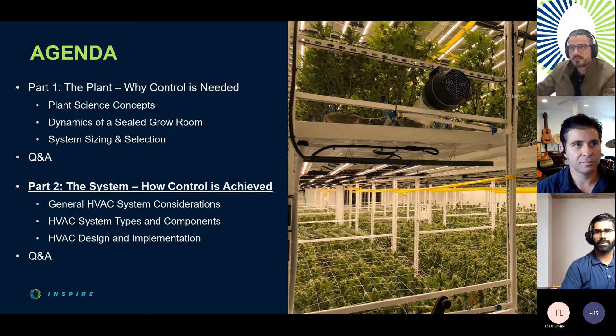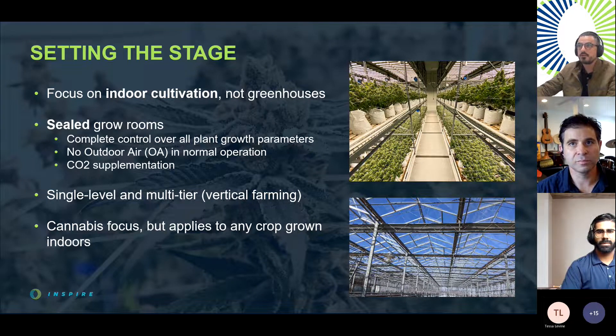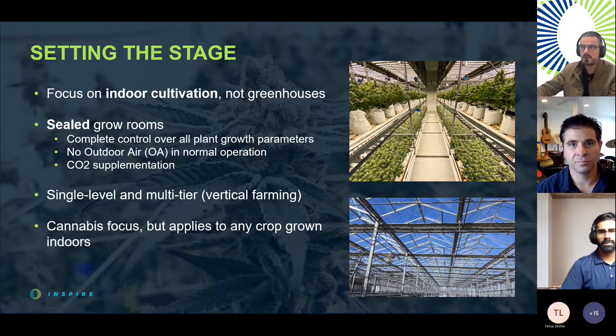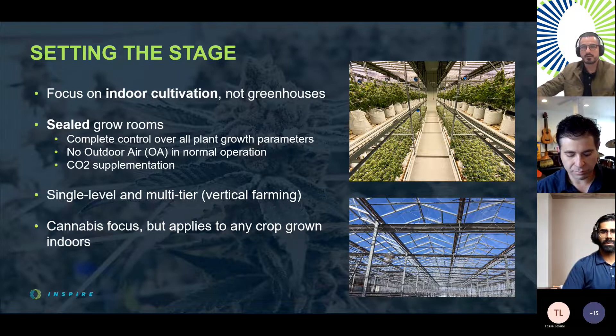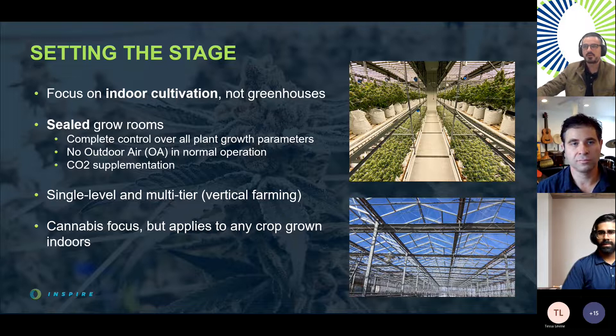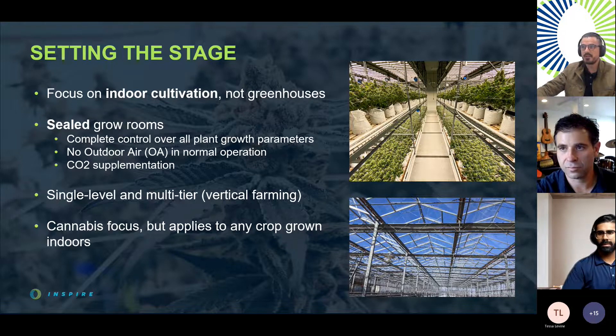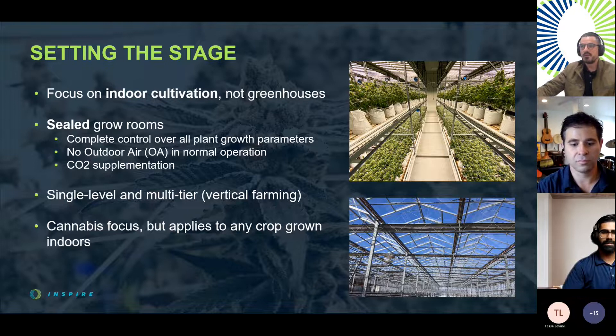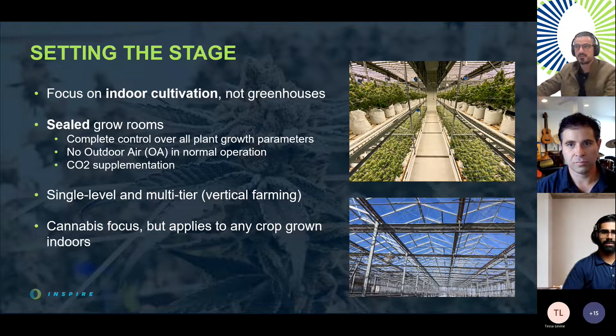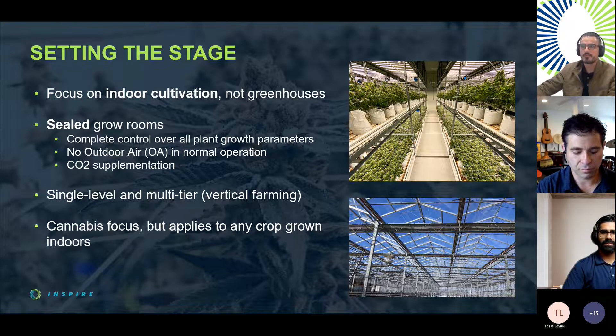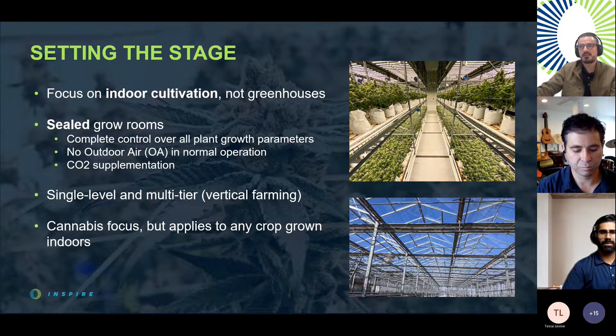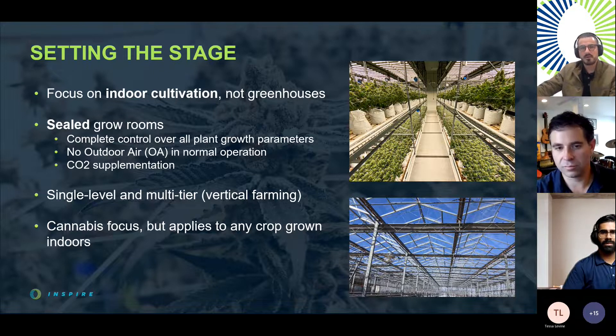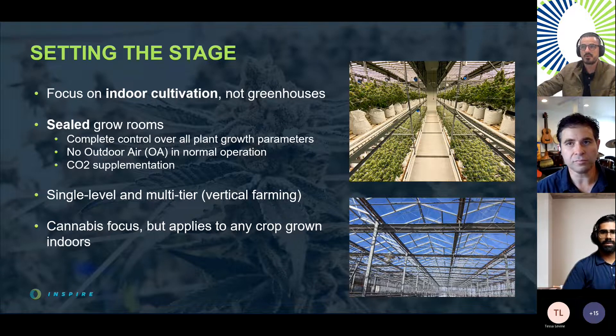Just to quickly set the stage, this talk will focus on environmental control for indoor cultivation only, not greenhouses. While many of today's concepts still apply to greenhouses, greenhouse environmental control strategies are for another talk. We're dealing with sealed grow rooms, where we have complete control over all growth parameters. There's no outdoor air in normal operation, and the air within the room is fully recirculating — mainly because we're supplementing the air with CO2 to maximize carbon assimilation and the growth rate of the plant. These sealed rooms can be either single-level or multi-tier, and the focus of today is on cannabis, though the core concepts apply to any other crop grown indoors.